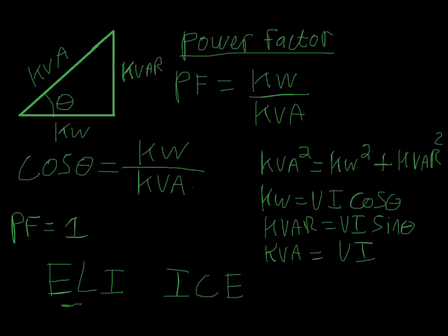So this is how you tell if your power factor is leading or lagging. The two aspects of power factor are the number and whether it's leading or lagging. Just by looking at whether it's leading or lagging, you can tell if you have an inductive system or a capacitive system. Like I said before, most of the time you're going to see an inductive system. We have yet to see a capacitive system.